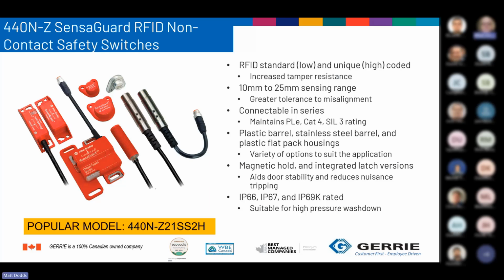For most non-locking door applications, I recommend SensaGuard. These are RFID coded switches and overcome issues with coded magnets such as attracting metal filings and direction of approach. Simply bring the actuator within the rated detection range of the switch and the outputs turn on. When connected in series, these are immune to fault masking with OSSD self-monitoring outputs. Additionally, because they are non-contact, except for the magnetic latch model, they are not susceptible to damage due to impact because they are solid state and they should never need to be replaced.